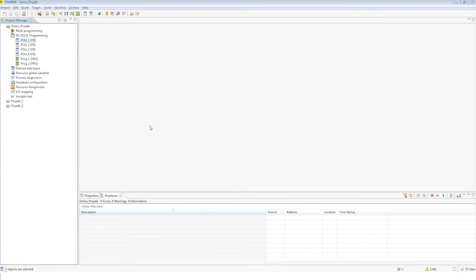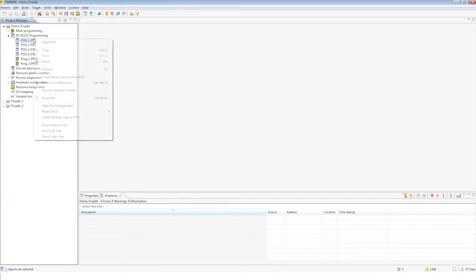Your blocks can be provided with Write Protection or Write-Read Protection. Please note that block protection cannot be undone, so you should create a backup copy of the unprotected block beforehand. You'll find the relevant commands in the context menu of the respective block via 'Protect POU.' If a block is sealed, not only is the selected block Write and Read protected, but all subordinate blocks become invisible and disappear from the Project Manager.